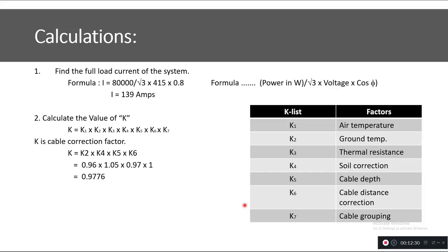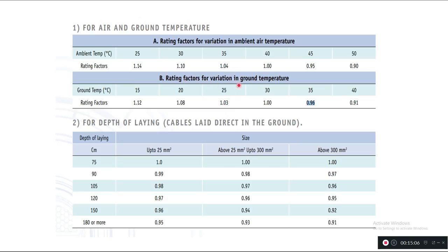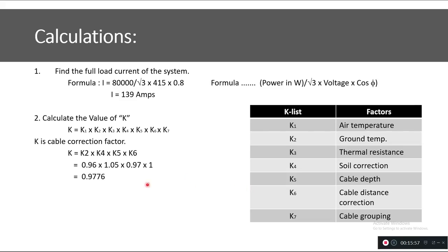To get the values of K2, K4, and K5, I refer to the cable manufacturer's datasheet. For a ground temperature of 35°C, the rating factor K2 is 0.96. For a laying depth of 1 meter (approximately 105 cm in the chart), K5 is 0.97. For damp soil, the soil correction factor K4 is 1.05. Multiplying these together gives an overall correction factor K of 0.9776.